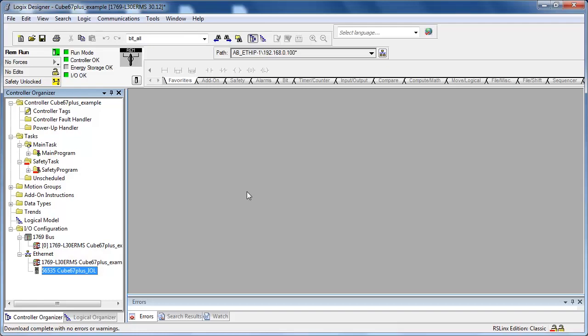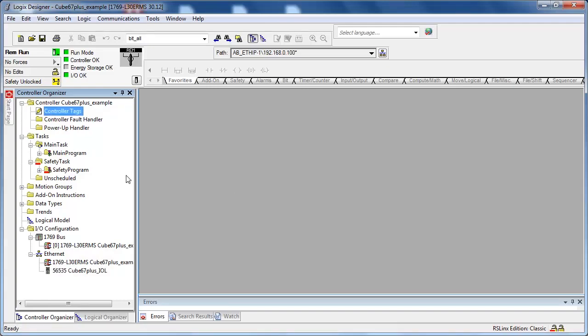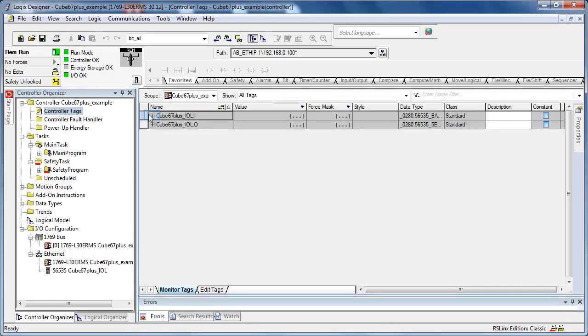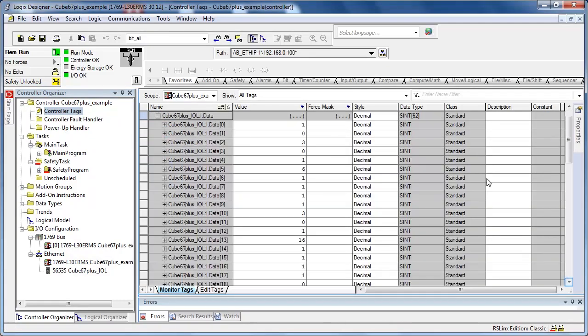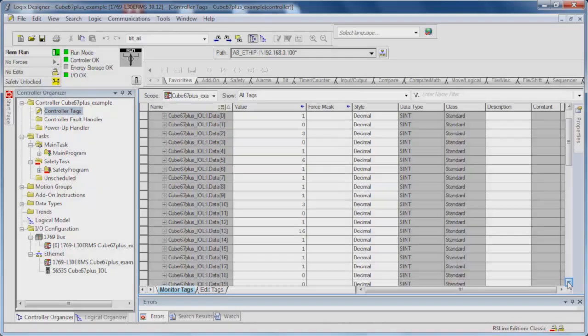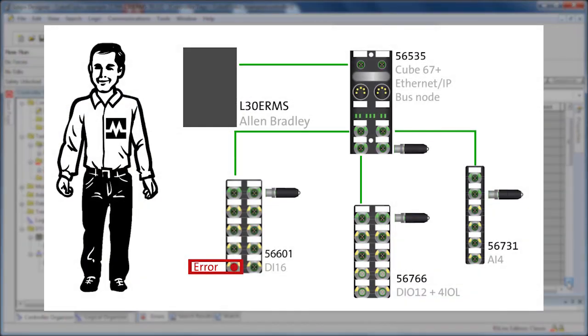If an error occurs on any IO module in the CUBE system, the diagnostic messages can be seen on the bus nodes and input data. In this case we cause two short circuits on port 6 of the 56601 module.